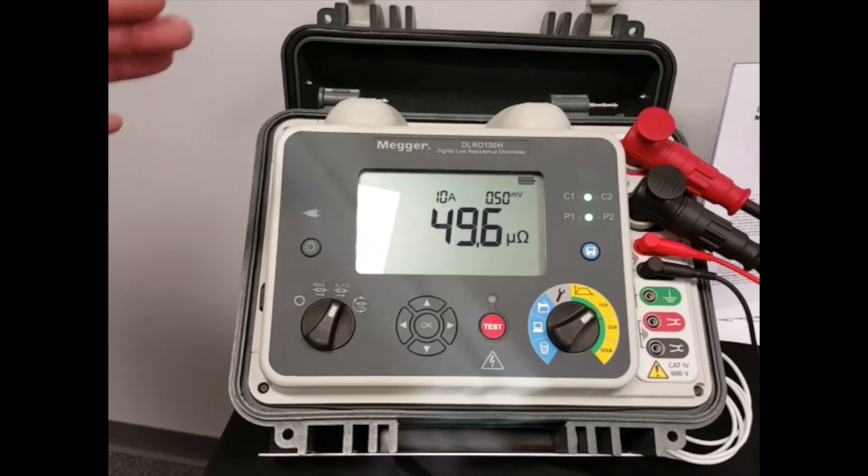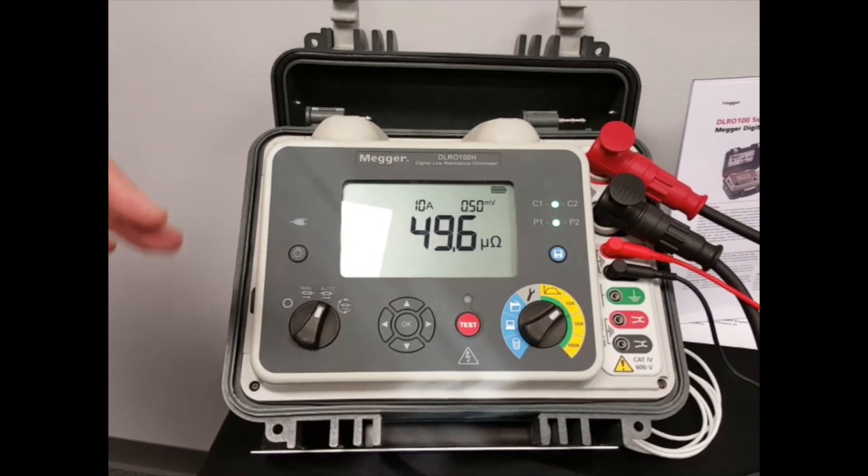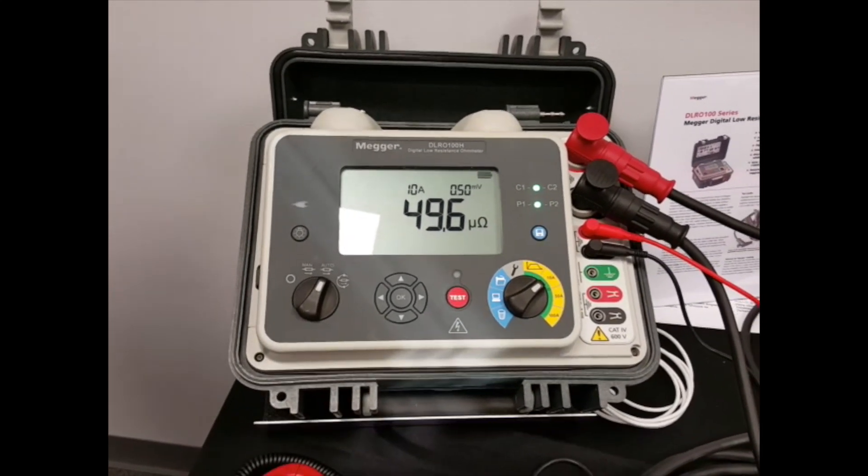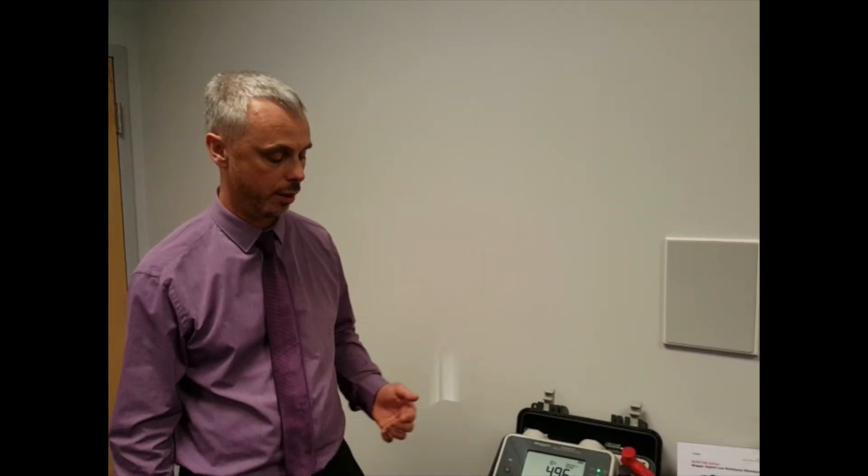So it ramps up the current, it holds it, it produces a very smooth DC output and then it will ramp down the test so that if you are testing a circuit breaker and it's still connected to a relay system, there's no way it will trip a relay system.